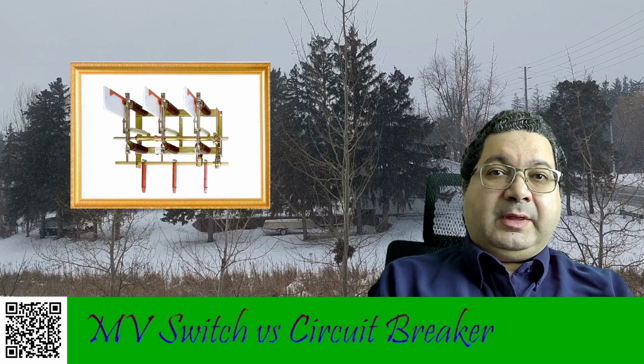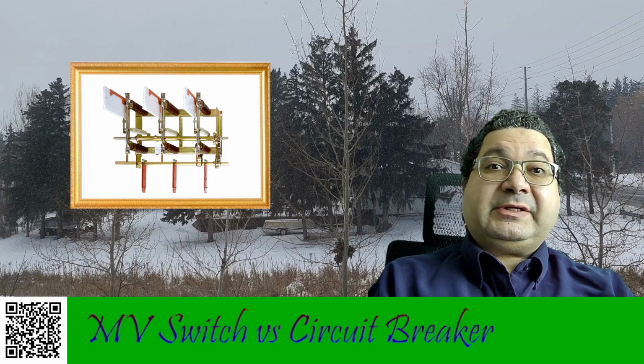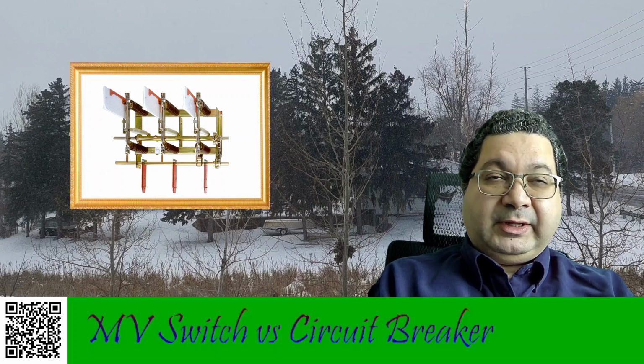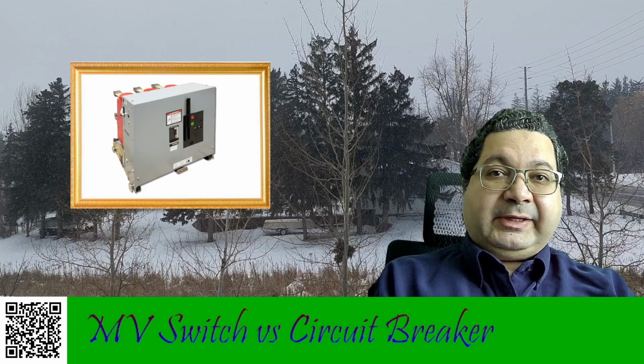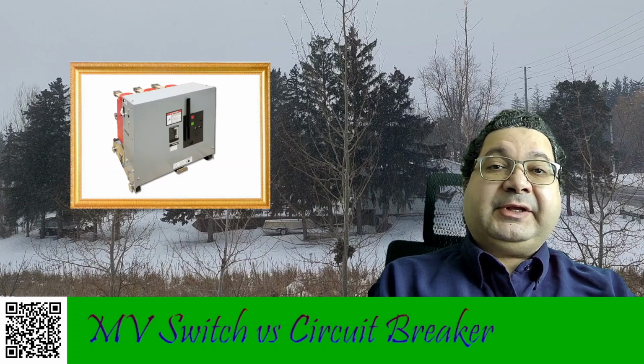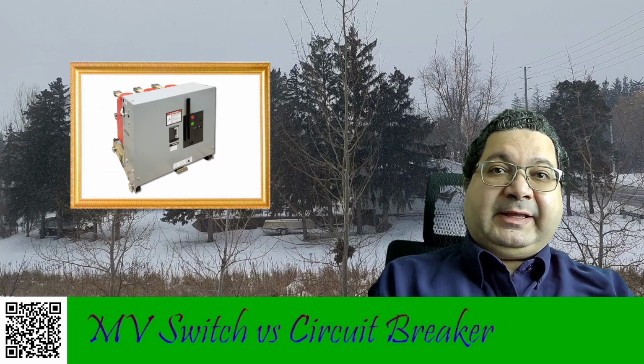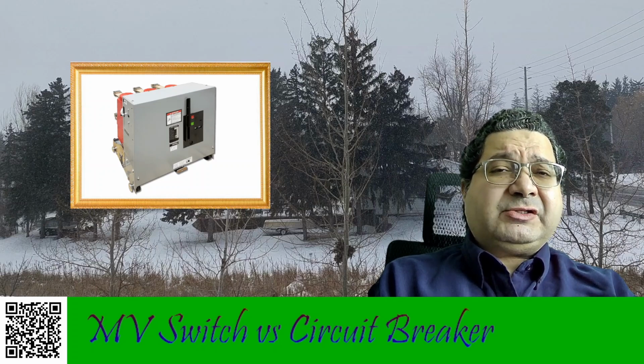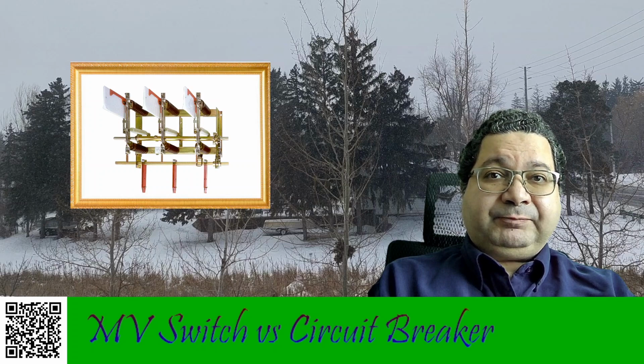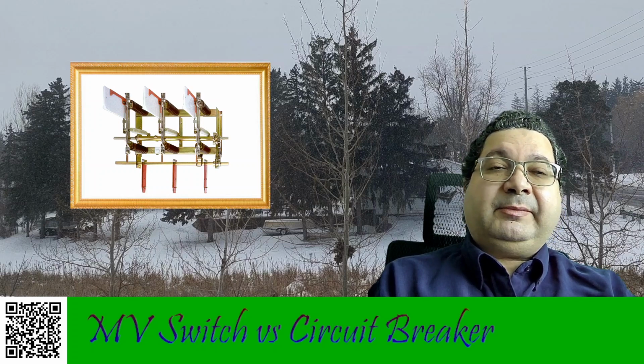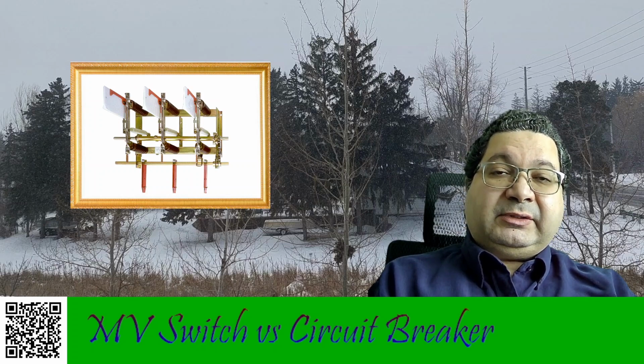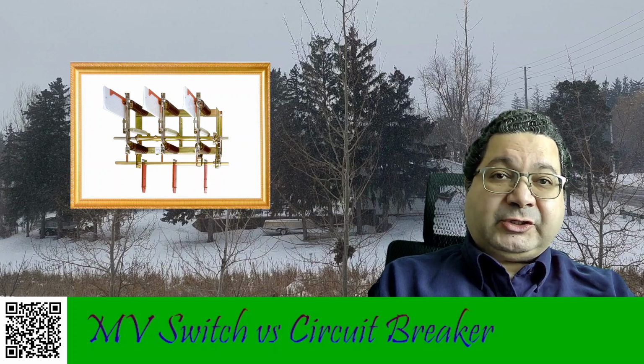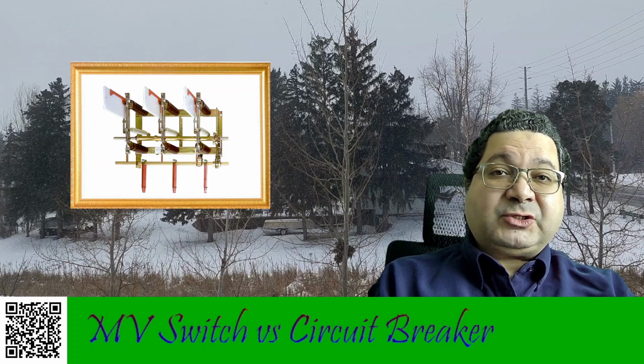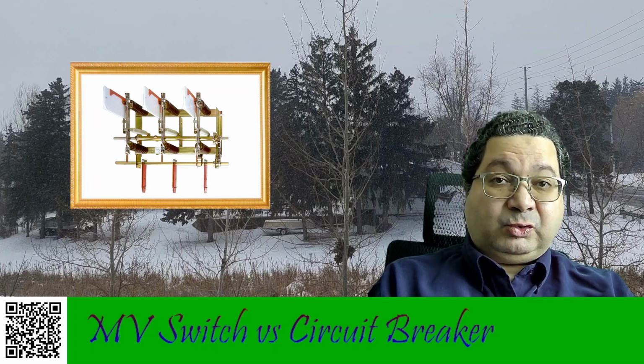However, a circuit breaker is designed mainly to interrupt load, so it can make and break the load, and it is rated for the voltage level. It can be used many more times than a switch. A switch is normally very limited in number of operations, probably 1,000 times of mechanical operation and maybe 100 times of actual operation on load if it is a load break switch.